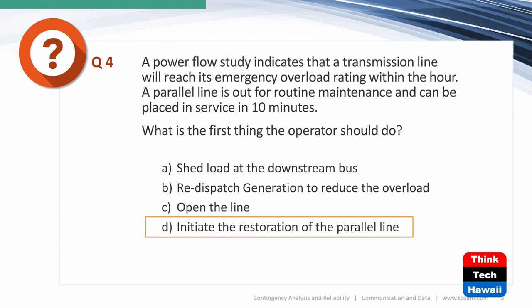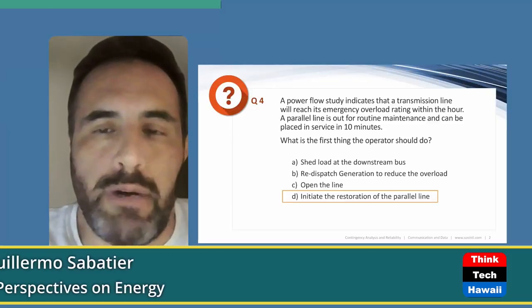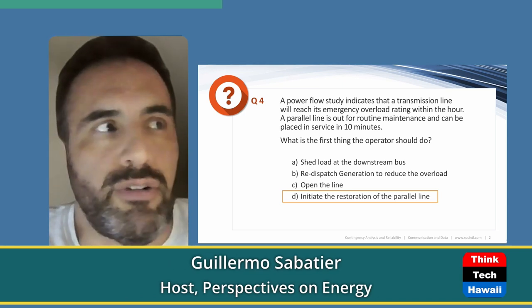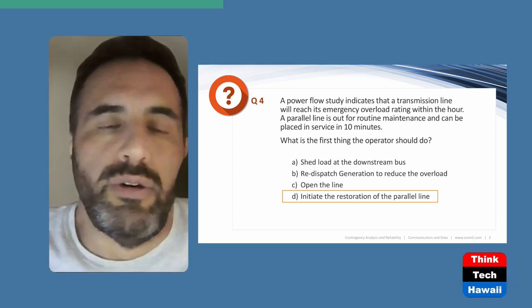Redispatching generation happens often in utilities that own both generation and transmission, but the question gives you no information about generator locations or which to ramp up or down — so B isn't an adequate answer here. The worst thing you could do is open the line — if you open it, that power is still flowing and it forces more power elsewhere, likely causing a worse problem. You're already down one line; removing another further aggravates the overload.